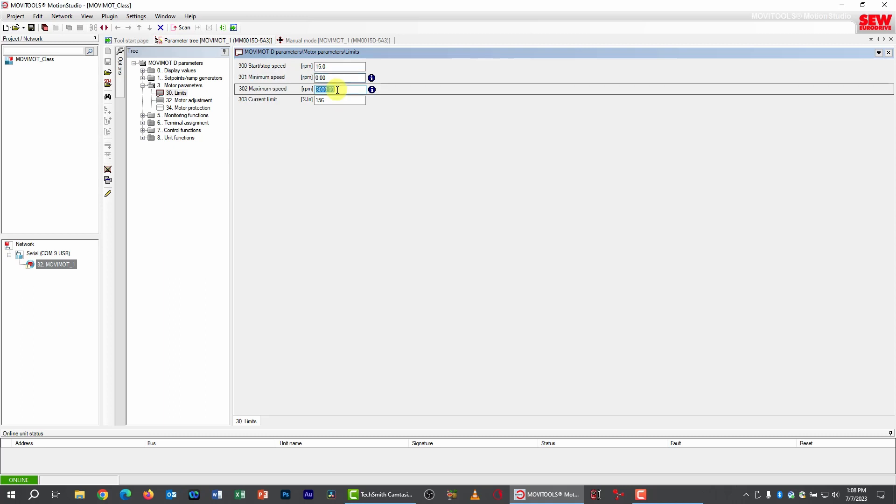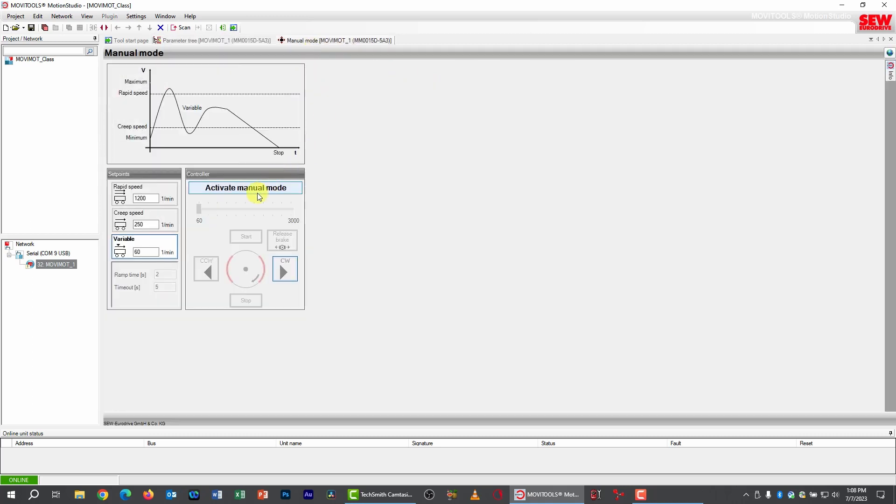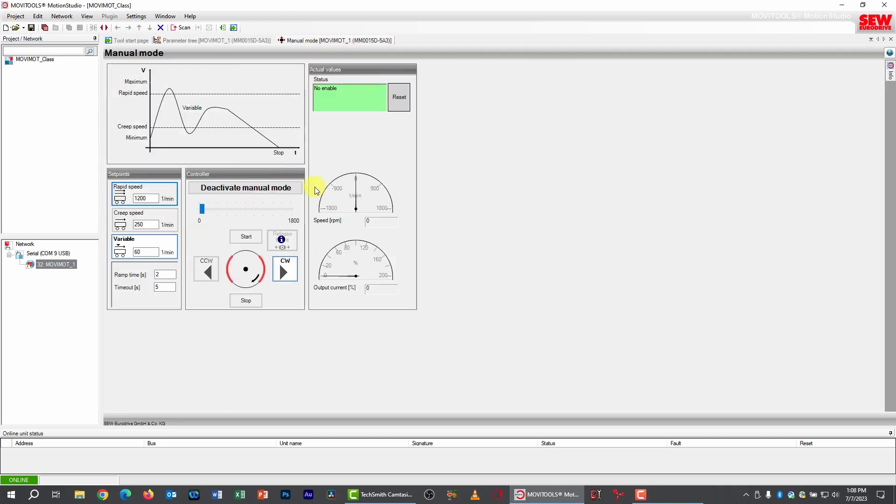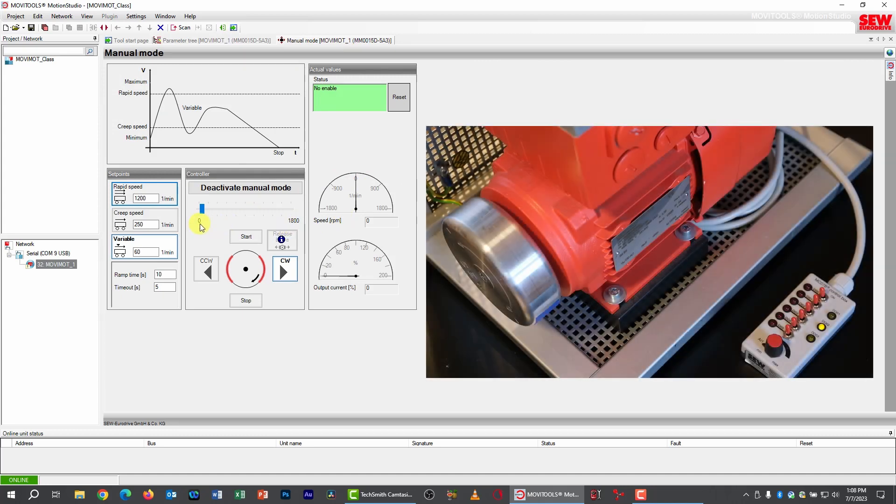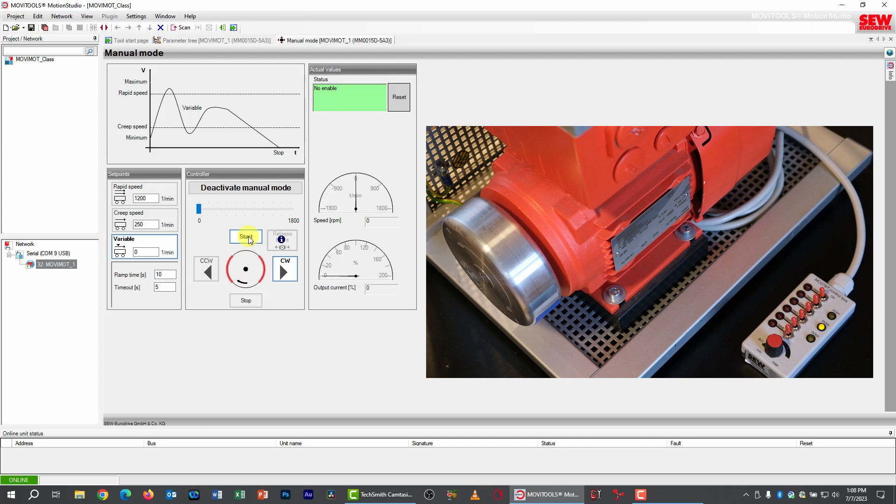So I'm going to change these to something else. I'm going to change minimum to zero and actually allow my drive to just be completely stopped. And I'm going to change maximum to 1800 RPM, which is my motor's nominal rated speed. And now if I go back to manual mode and reactivate it, you'll notice that the limits have changed and now it reflects what we've programmed in. Now I need to adjust my slider here. I'm going to move that all the way down to zero, and I'm going to click the start button. You notice that the brake releases.